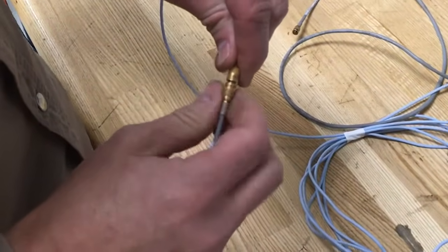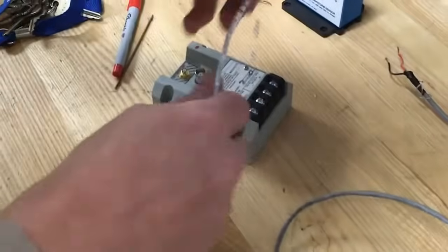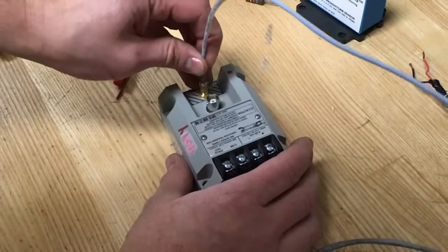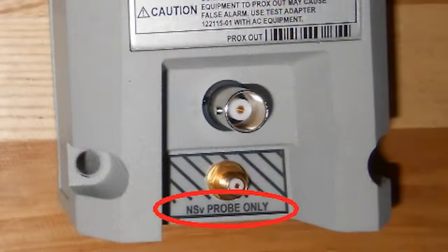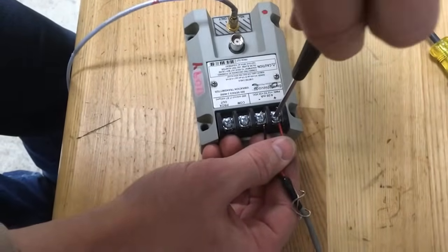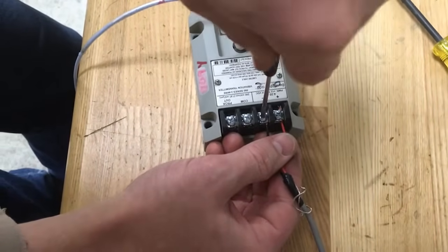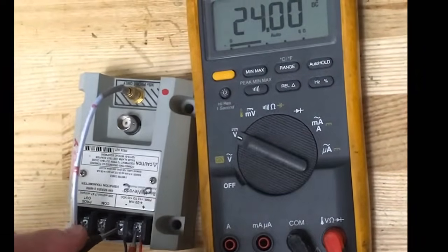If your probe is not already connected to a proximeter, go ahead and do so now. Ensure the extension cable is of the correct type and length, and that the probe and cable are both compatible with the proximeter. Ensure the device is powered with the proper voltage. In this case, it is a loop-powered vibration transmitter, which uses 24 volt DC.